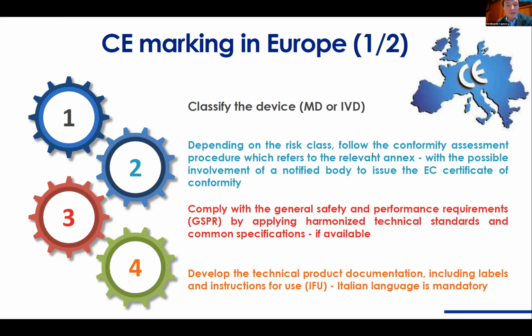After deciding the risk class, you will have to follow the general safety and performance requirements, stated in Annex 1 of the new regulation, which is a checklist stating all the fundamental characteristics your device must have depending on its specific type.